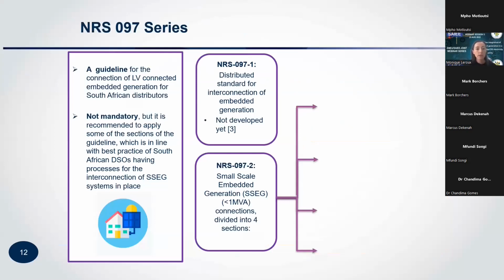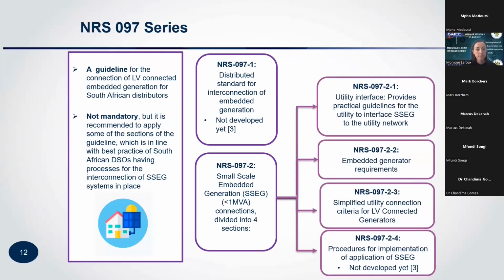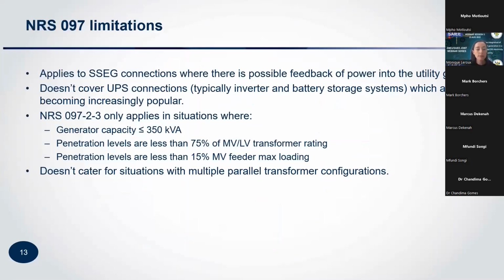Okay, just quickly on the NRS 097 series, I won't go into much detail for this. The guideline is specifically focused on LV connections, and it is important for municipalities to remember that this is not the standard, so it's not mandatory, but it does give a good recommendation that can be applied by municipalities on what is the best practice of getting SSEG onto the network and what should be considered. Okay, then just some limitations on the NRS 097: it applies to SSEG connections where there's possible feedback onto the utility grid. It doesn't cover UPS or battery installations, which are obviously becoming increasingly popular.